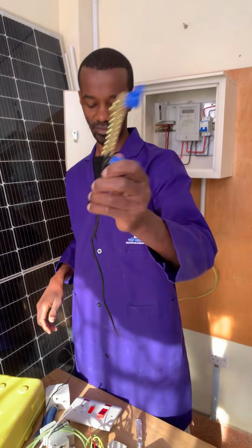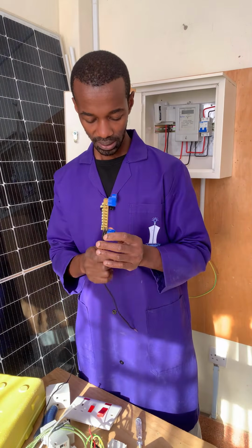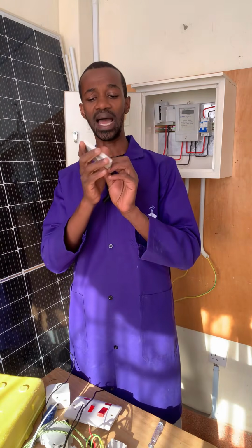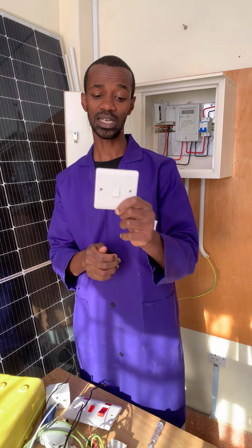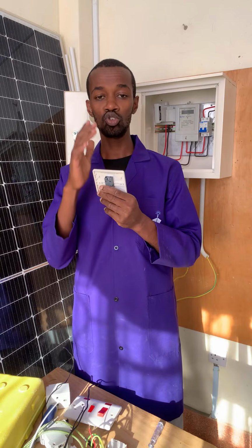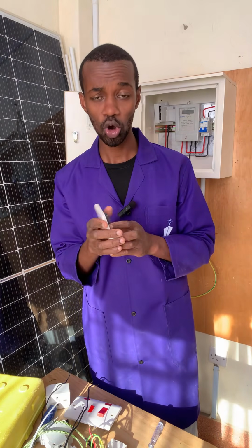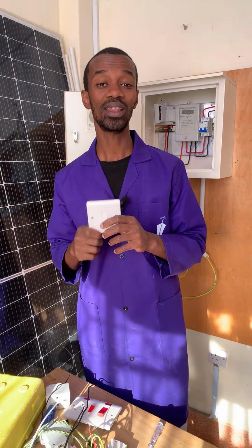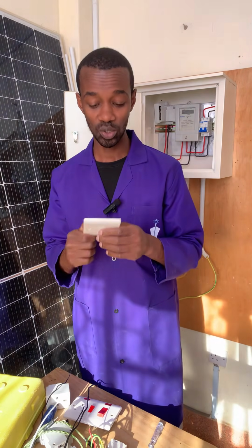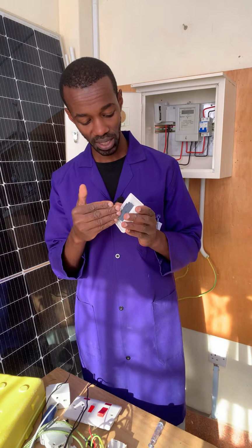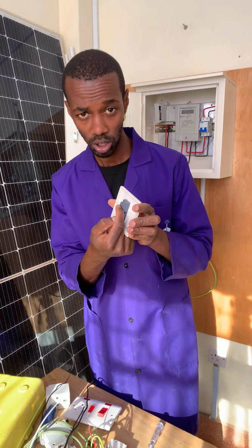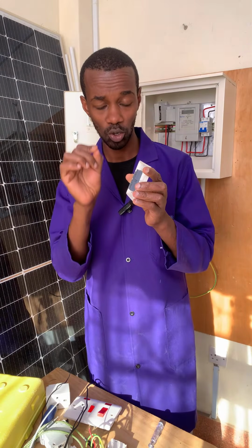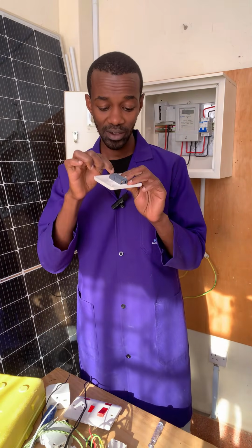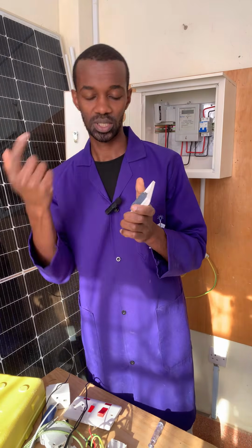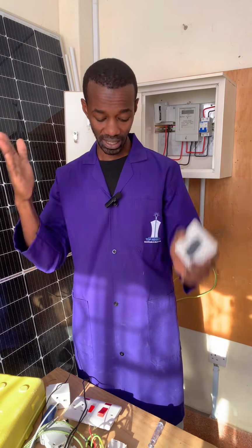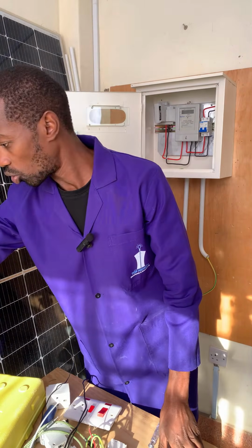So we have agreed there has to be tight connections here. In many cases, a loose connection at the switch, especially for lights, does not necessarily lead to dimming of that light, because at the switch, in many cases, the switch has the common connection, where you feed the mains from the consumer unit. Whenever you connect it at the common, the output is also a line which is connected to the lights, or that bulb.